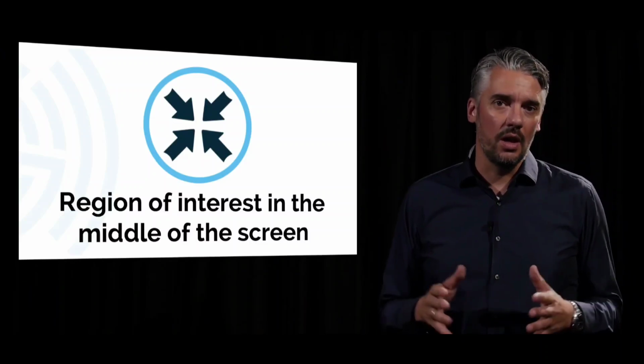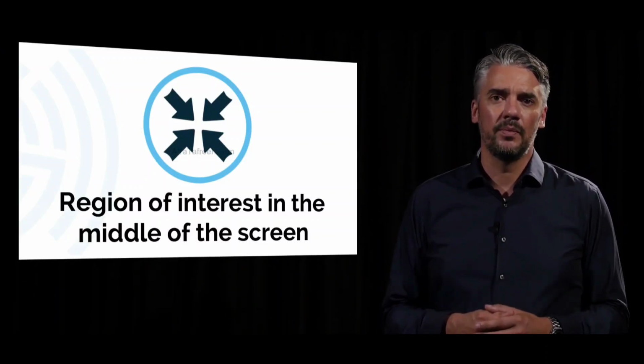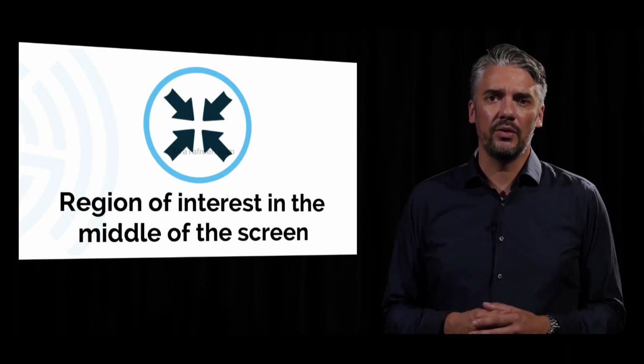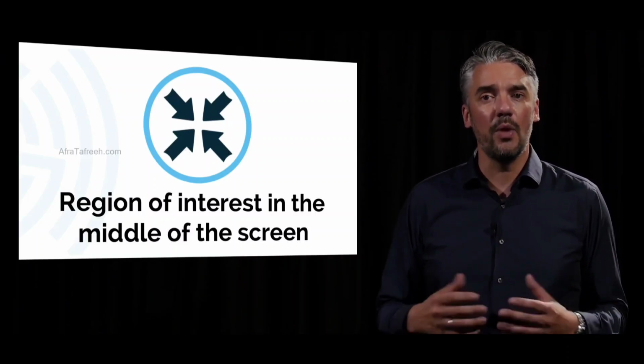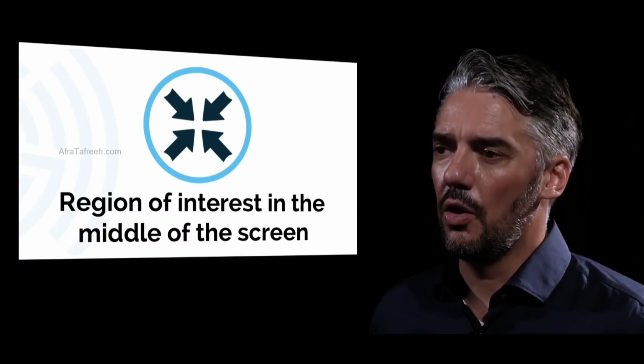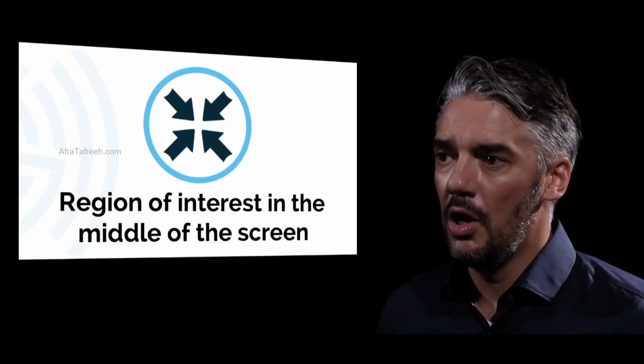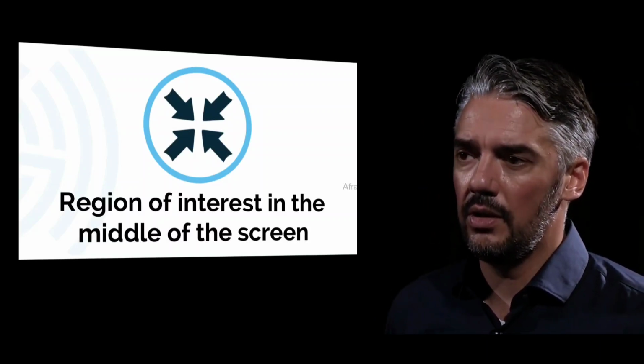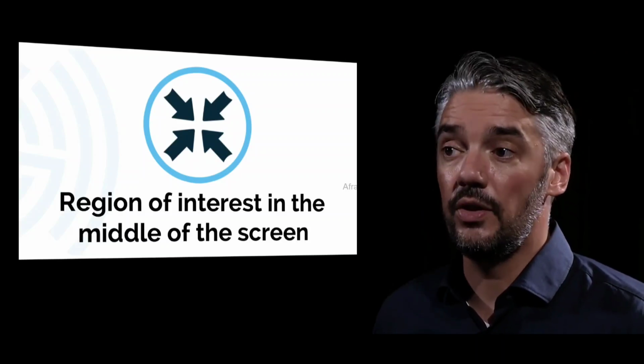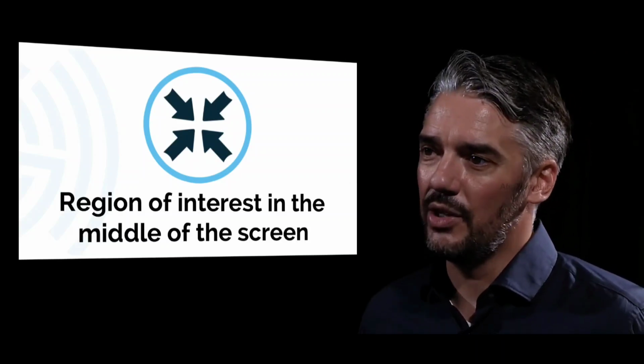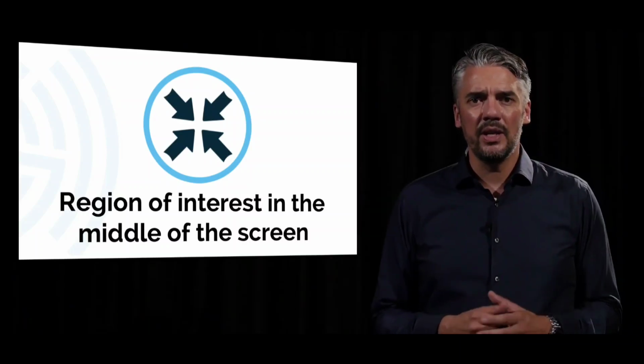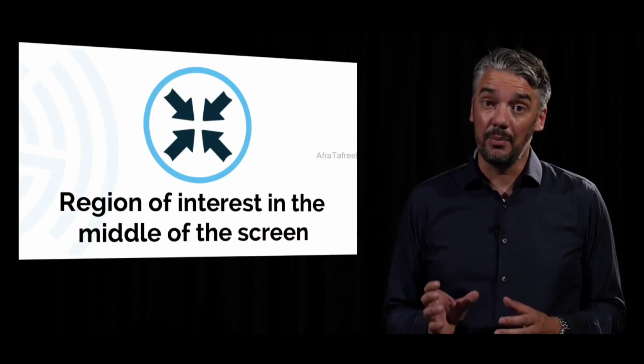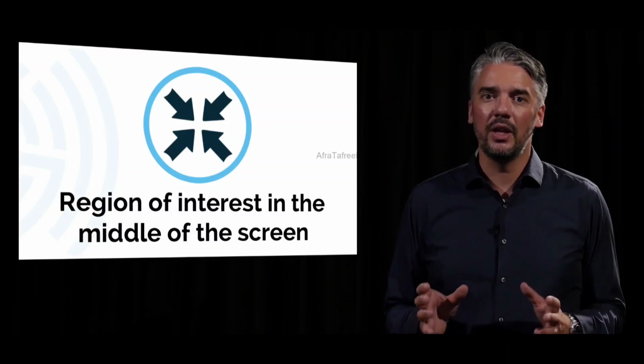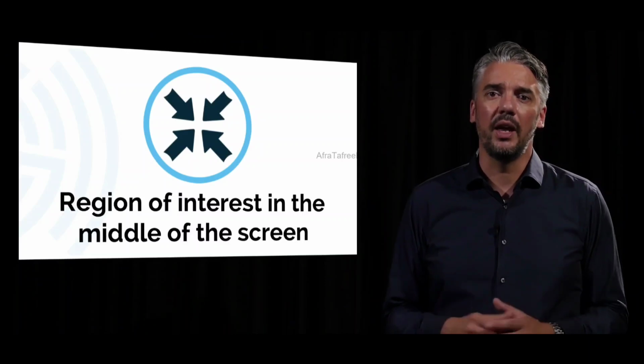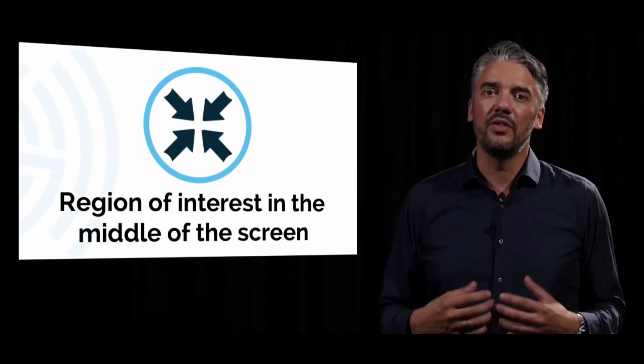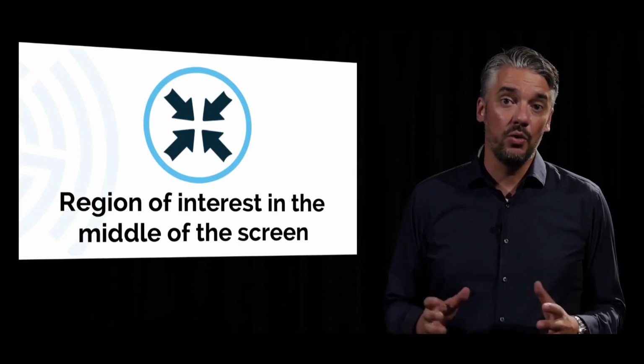When scanning, you would like to have a good overview of the whole region. You don't only wish to see the region of interest, but also the structures and tissues surrounding it. It's important for your diagnostic or evaluative process and your clinical reasoning to see the overview, the functional relation, and to see the quality of all structures and tissue visualized. Therefore, the region of interest should be centered. Centering the region of interest on the screen and maintaining that position during live scanning is a transducer skill that should be practiced when first starting to scan. It's also needed to prevent the desired image from repeatedly drifting out of view when scanning more rapidly.